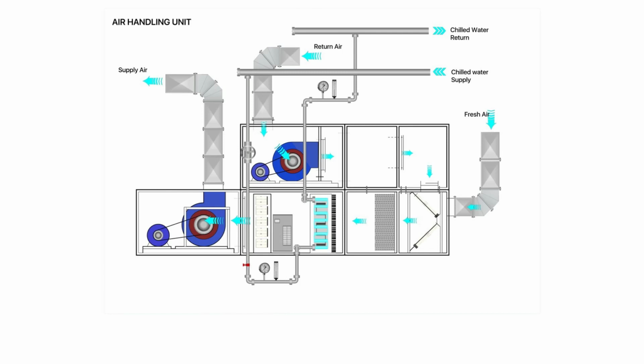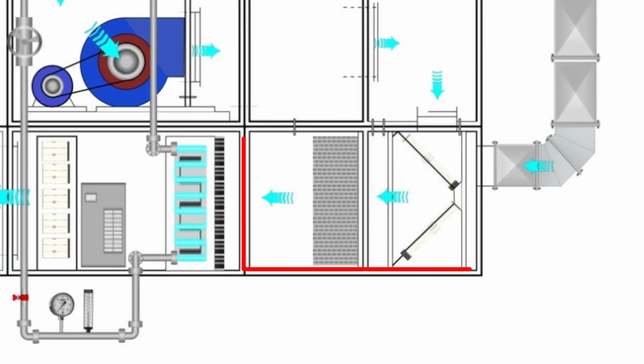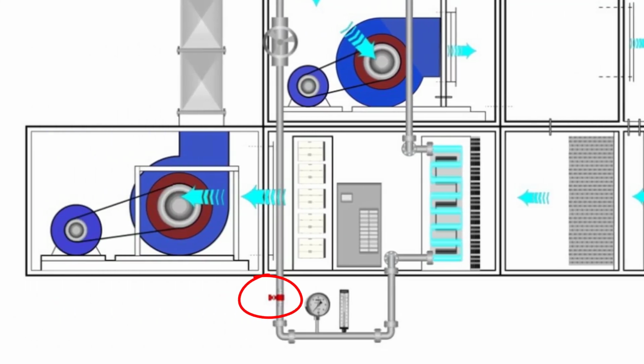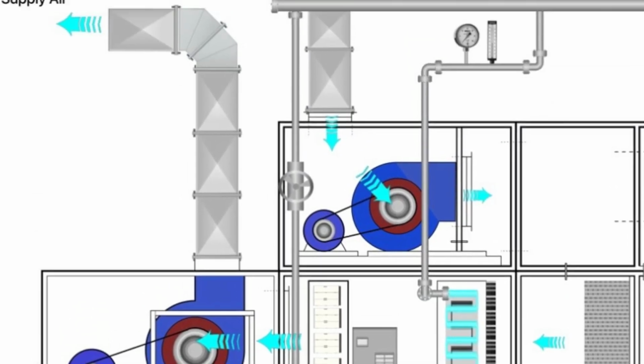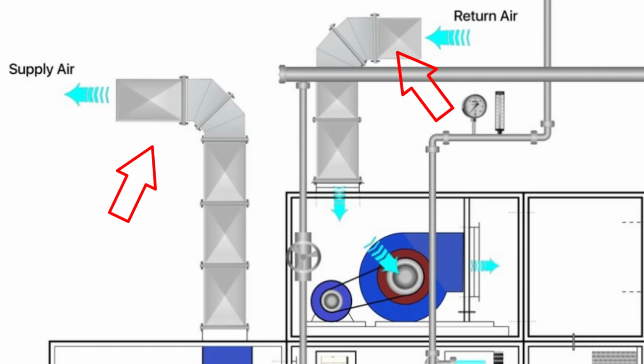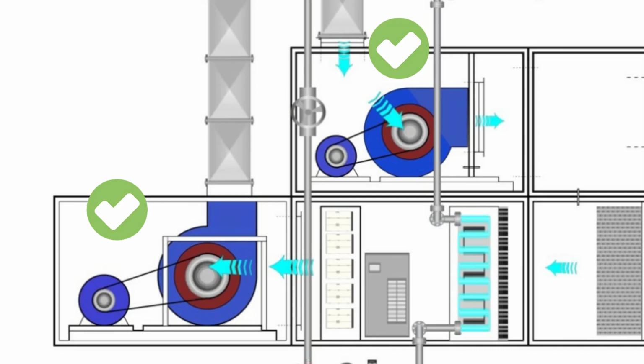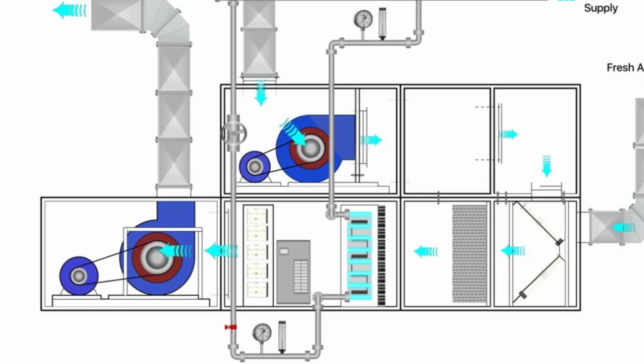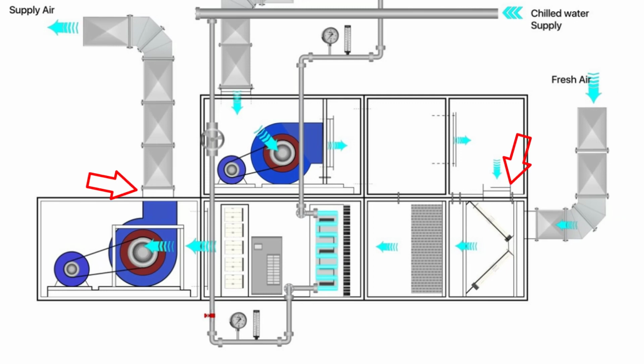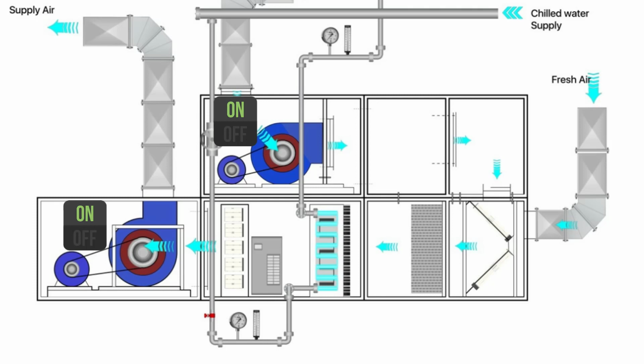Okay, now let's enumerate the tasks that require a monitoring device or a sensor in accordance with the components of the AHU system. Number 1, we need to monitor the filter status. If the filter gets dirty, an alarm will energize as a block filter alarm. 2, the butterfly valve for chilled water supply should be motorized and have an automatic function. 3, we need to monitor the supply air and return air temperature, humidity, pressure, and velocity. 4, we have to install airflow status for the supply fan and return fan. 5, damper actuators should be installed in the supply air damper, return air damper, and fresh air damper. And number 6, supply fan and return fan status.